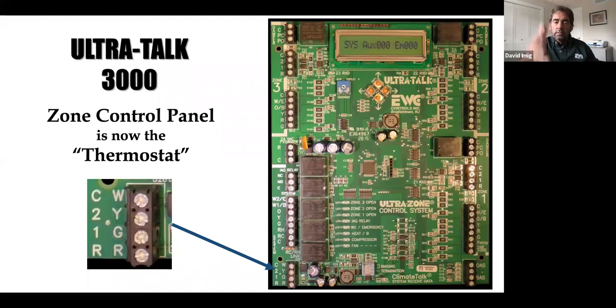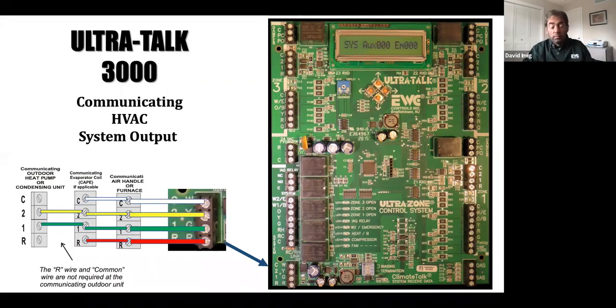The zone control panel, and let's take a tour around this board. The zone control panel becomes the thermostat. What does that mean? That means that the equipment believes you're tying it into a thermostat. The same exact wires that you would run up to a thermostat in a non-zoned application are the same wires that you run to this zone panel. In this particular case, you're bringing your 4 communicating wires up from your zone, air handler and or furnace, connecting it into the communicating terminal in the lower left-hand corner.